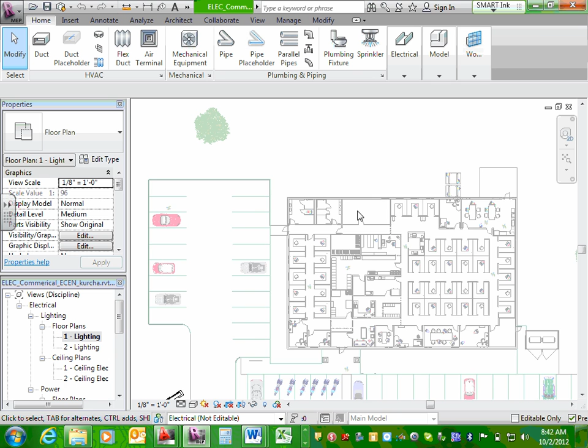So I think we can go to the scope now. It's a 10,000 square foot building. We want you to design for a 5,000 square foot addition, so keep that in mind when you're sizing your service. If you come up with 370 amps, don't put in a 400 amp service, because then we won't have any expansion capacity for when we do add this 5,000 square foot addition.